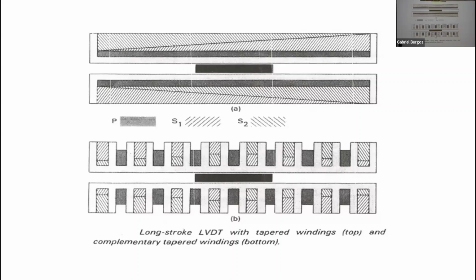That parameter is called the stroke to length ratio. The simple bobbin LVDTs, like I showed you at the beginning, are relatively long compared to the stroke they measure. But the aerospace type LVDTs are made so that they can be relatively short. A bobbin type LVDT with 3 windings separated can only do, at maximum depending on factors, at least 50% longer than the stroke of the LVDT, maybe lots worse. But with a taper winding, you can get up to 80 or 85% stroke to length ratio, so it doesn't have to be much longer than the length.